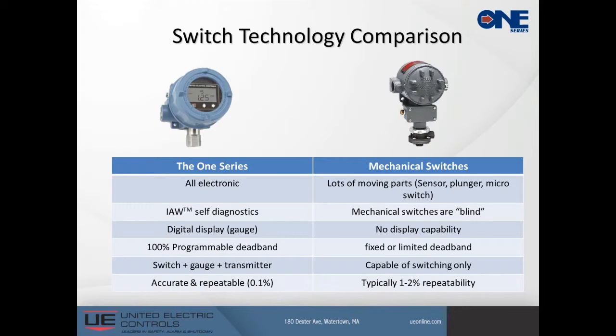So we'll talk a little bit about how we're going to address that HART scenario here in just a moment. Again, just real quick, if you're going to compare electronic to mechanical, here are some of the benefits of the One Series over the mechanical switch. So all electronic, no moving parts, it's self-diagnostic, it's got the digital display, 100% programmable, including the deadband. It's a switch, it's a gauge, it's a transmitter. And the accuracy is 0.5%, repeatability is 0.1%.